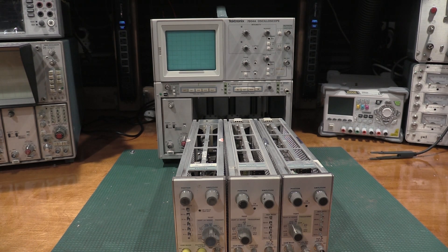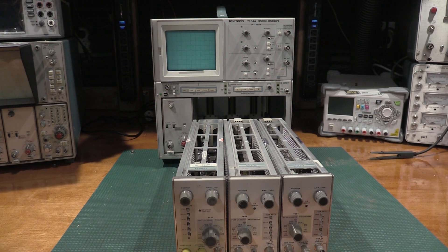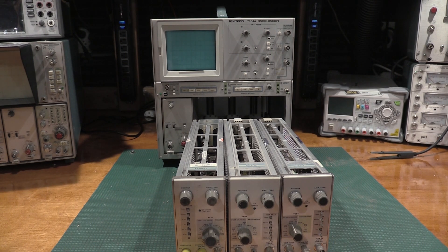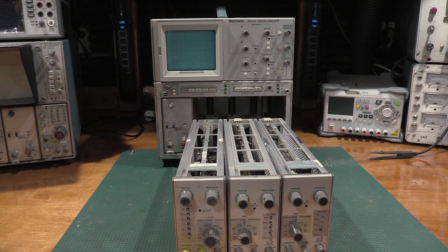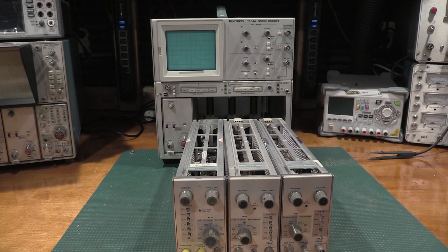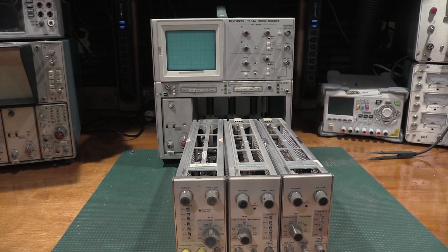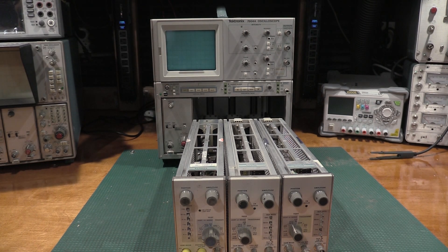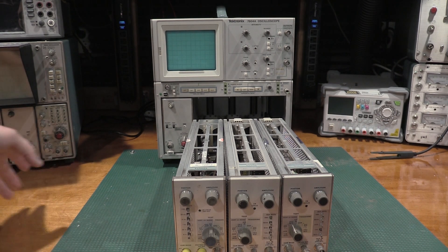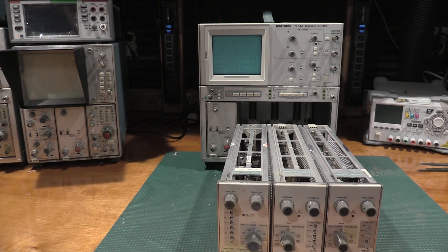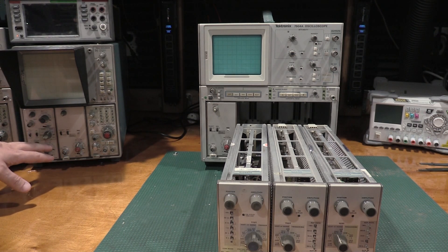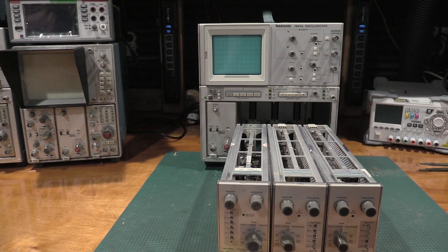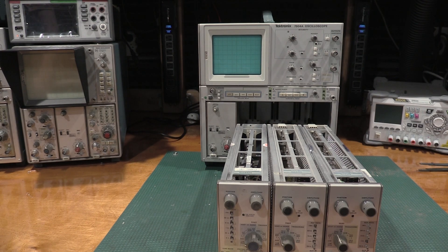So we'll start off with do you actually need a calibration fixture to work on a 7000 series scope. The answer is no you don't but you do lose one of the powers of a 7000 series scope. You can do the full alignment on a 7000 series with and this is true for all of the 7000 series except possibly the 7854. You can do a full alignment frame and everything with a time base and a vertical plug-in. So we'll use the 7603 that I use as a daily driver as an example. I could align this scope with these plug-ins and that'll be just fine. The measurements will be valid, everything will be good, it'll meet spec, all of that stuff that's good.